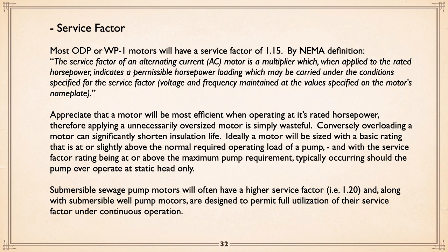Ideally it should be sized with a basic rating that is at or slightly above the normal required operating load of a pump, and the service factor being at or above the maximum pump requirements, typically occurring should the pump ever operate at static head only. And basically that's how I would size a motor, so that you're at or slightly below rating over the normal operating range you anticipate. Then have the service factor. Hopefully that's enough to allow the motor to operate if you're at static head only. If it isn't, then you have to upsize the motor a bit.